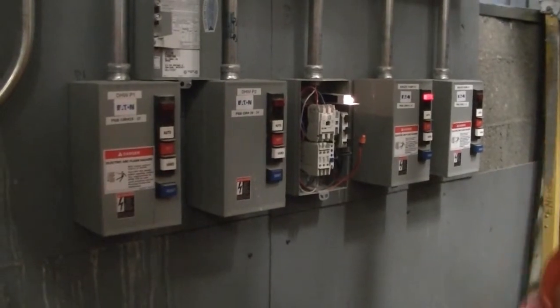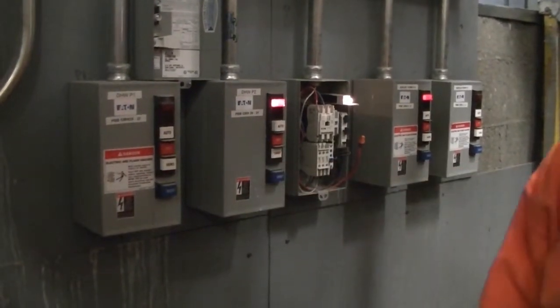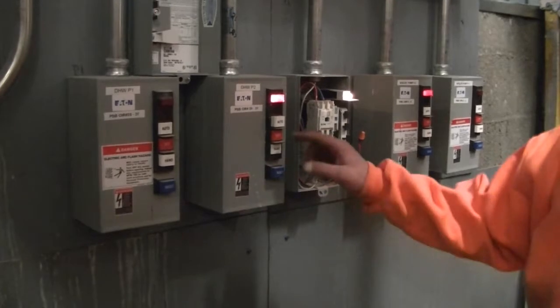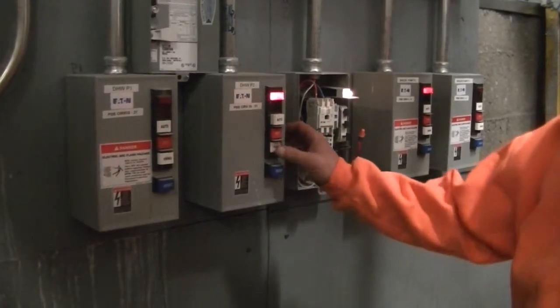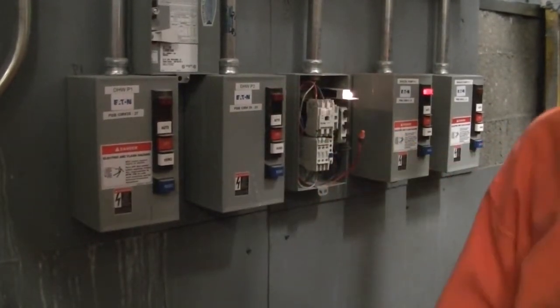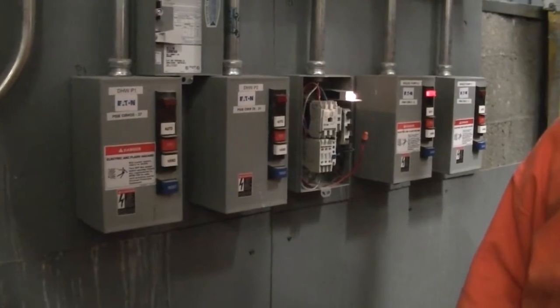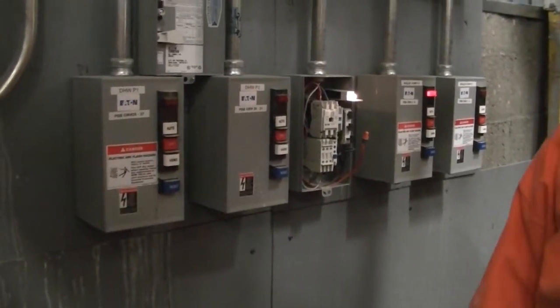If you don't feel like waiting, you can push the hand button just to make sure the pump fires up. Now you know it's not a problem with the pump. Put it back in auto, reset your boiler, fire it up, and then make sure the pump comes on, okay?